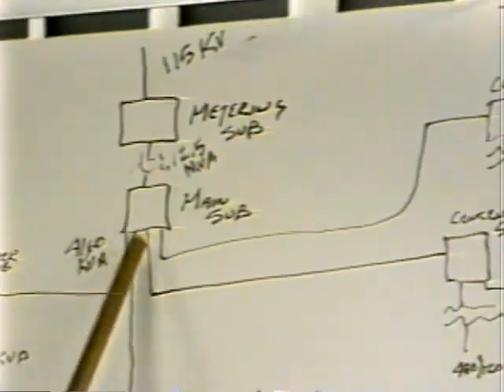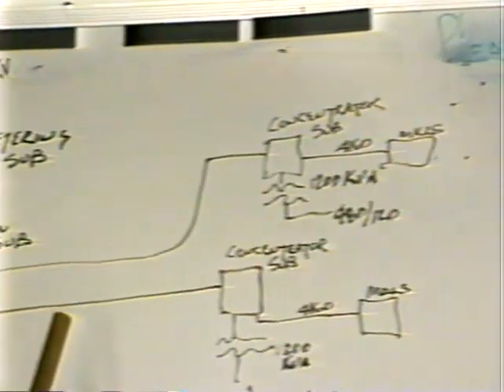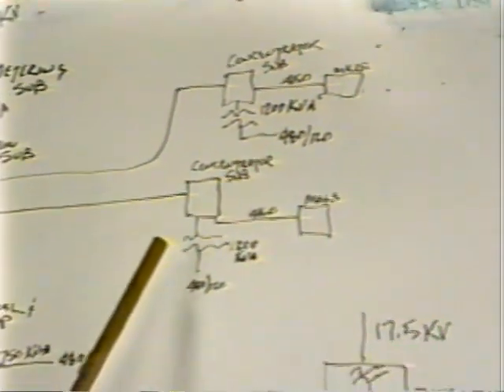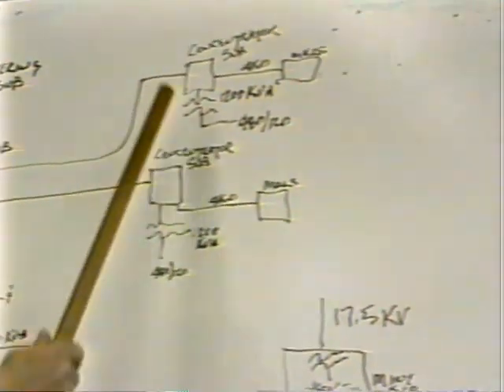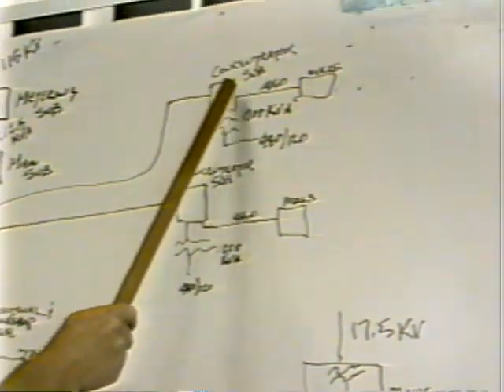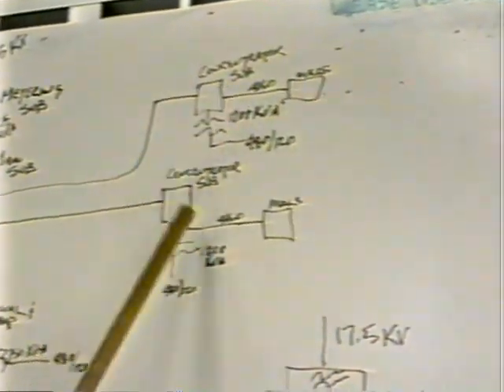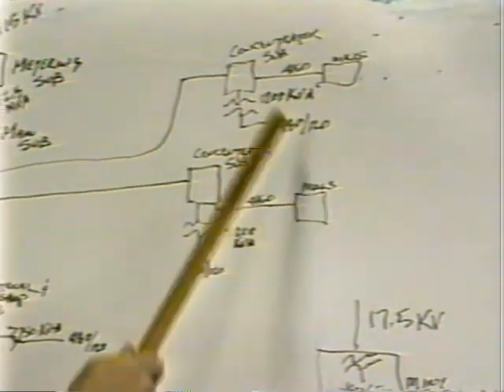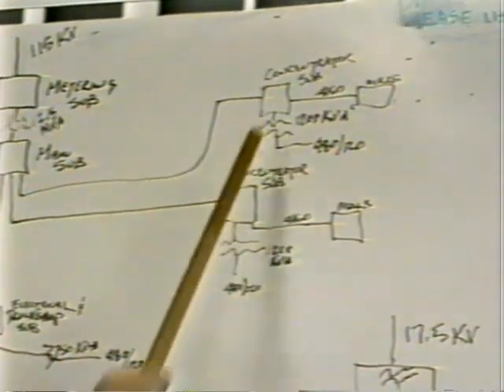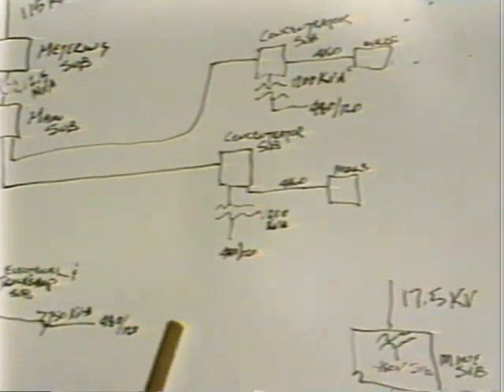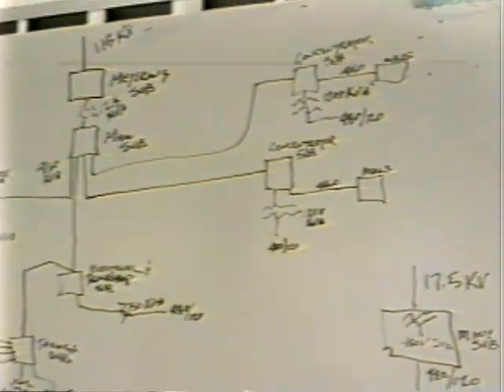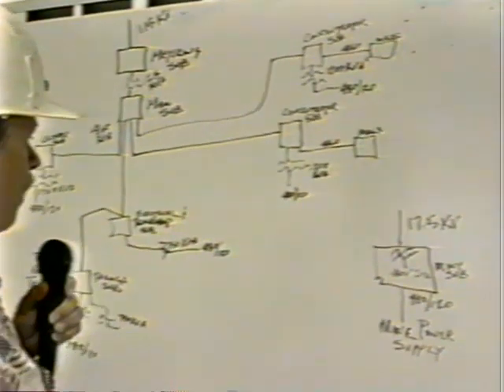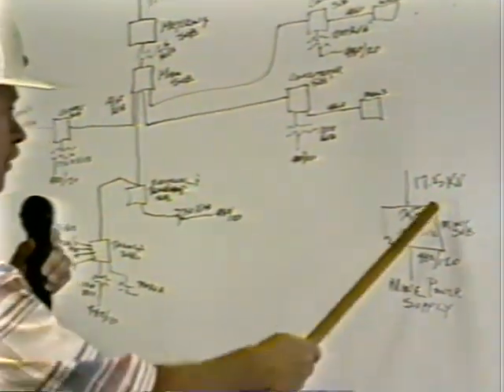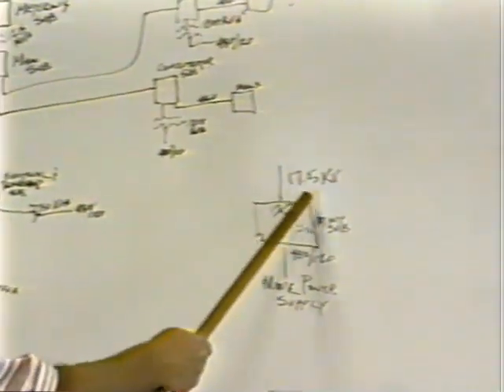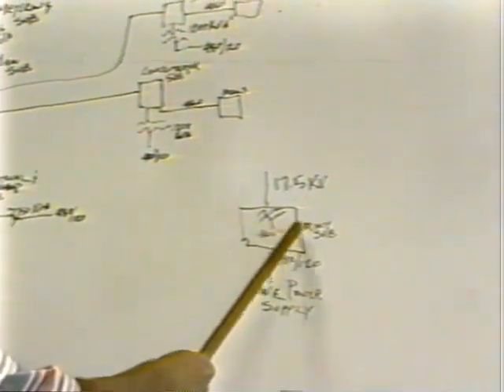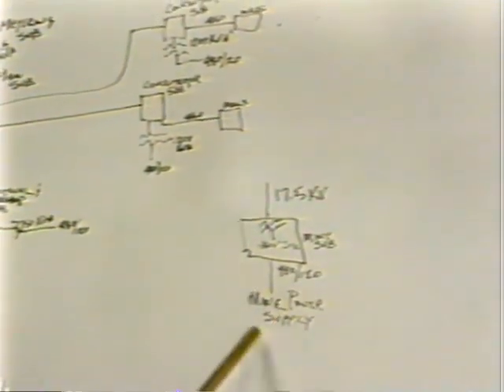We have 2 feeders coming out of the main sub, 4160 volt feeders that feed 2 areas of the concentrator sub. Those 4160 feeders are broken down to 2 feeders that feed 2 mills on one sub, 2 feeders that feed 2 mills on the other sub, and we have 2 1200 kVA transformers that distribute our 480 volt, 120 volt system on the floor. Also out in the mine, we have 1 substation out there that's fed from our 17.5 kV. It has a transformer that distributes it down to 480 volt that comes out and feeds a mine power supply.